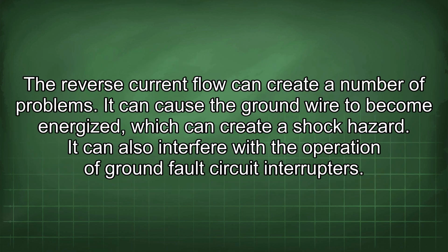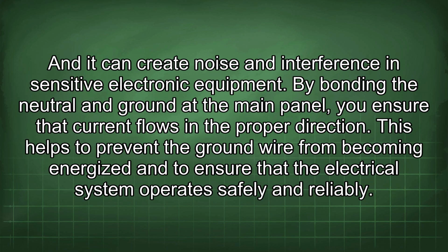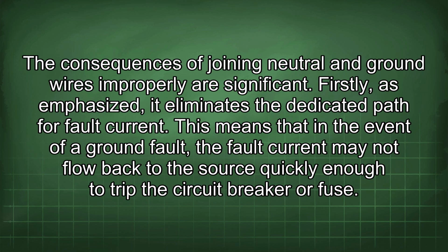The reverse current flow can create a number of problems. It can cause the ground wire to become energized, which can create a shock hazard. It can also interfere with the operation of ground fault circuit interrupters, and it can create noise and interference in sensitive electronic equipment. By bonding the neutral and ground at the main panel, you ensure that current flows in the proper direction. This helps to prevent the ground wire from becoming energized and to ensure that the electrical system operates safely and reliably. The consequences of joining neutral and ground wires improperly are significant.